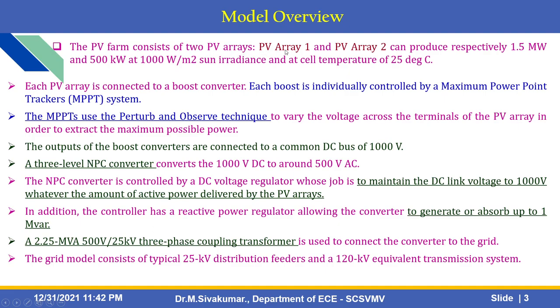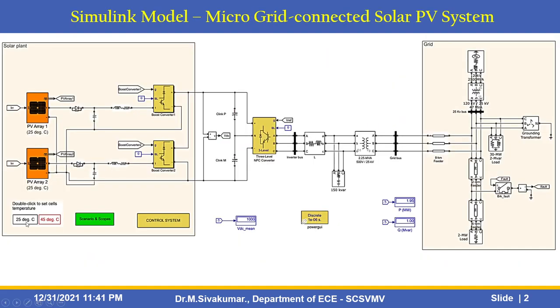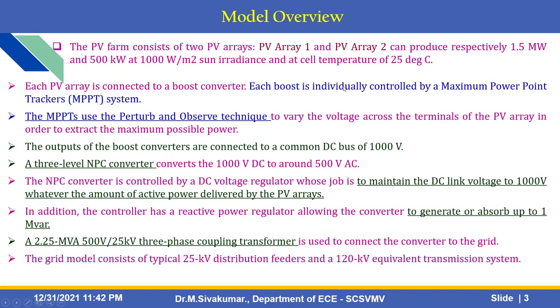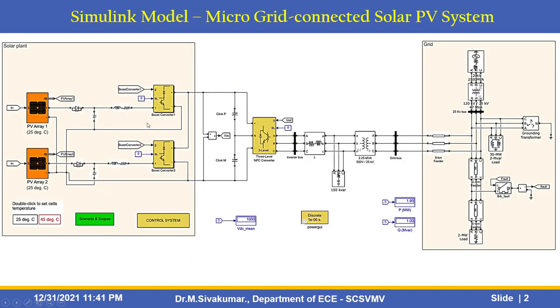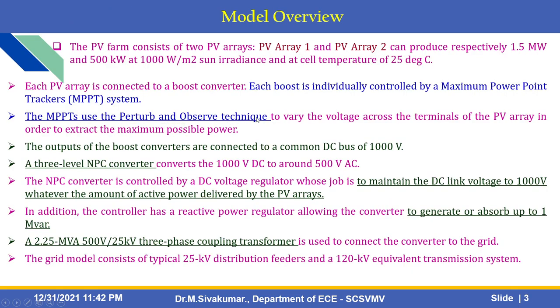The PV farm consists of 2 PV arrays: PV array 1 and PV array 2. They can produce respectively 1.5 MW and 500 kW at 1000 W/m² solar irradiance at cell temperature of 25°C or 45°C. Each PV array is connected to a boost converter — boost converter 1 and boost converter 2 — each individually controlled by a maximum power point tracker system.